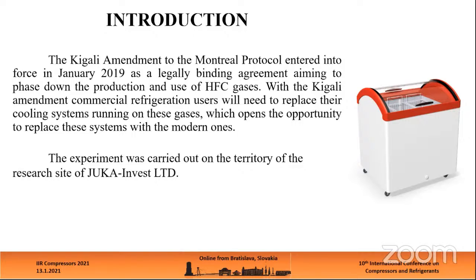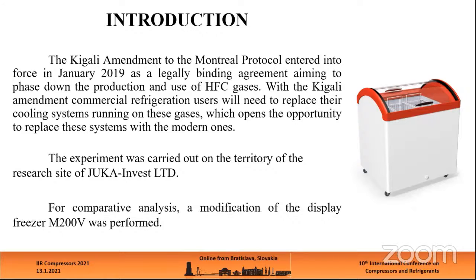Introduction. The Kigali Amendment to the Montreal Protocol entered into force in January 2019 as a legally binding agreement aiming to phase down the production and use of HFC gases. With the Kigali Amendment, commercial refrigeration users will need to replace their cooling systems running on these gases, which opens the opportunity to replace these systems with modern ones. The experiment was carried out on the territory of the research site of Yuka Invest Ltd. For comparative analysis, a modification of the display freezer M200V was performed.